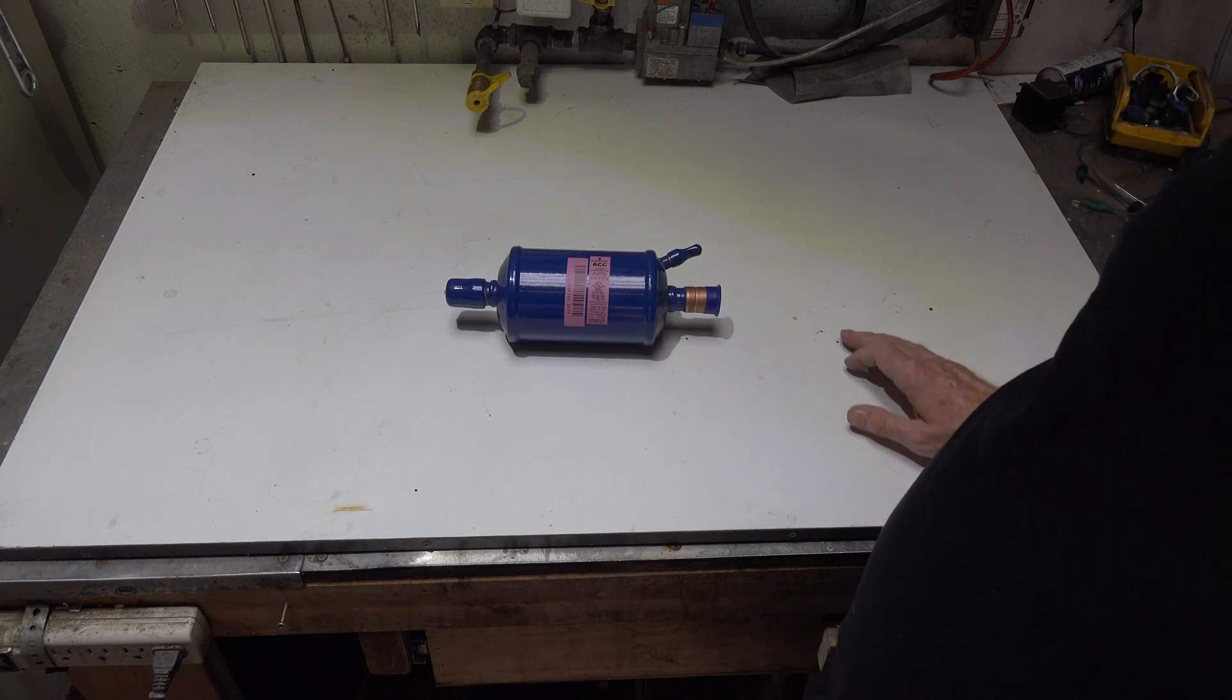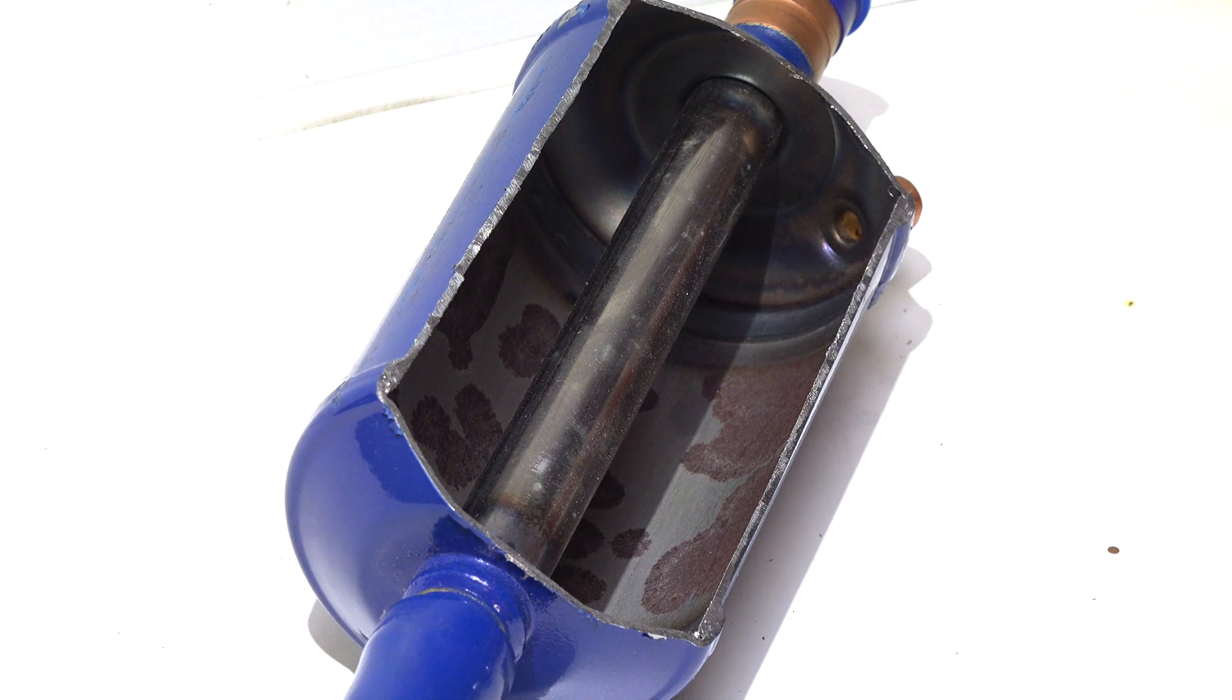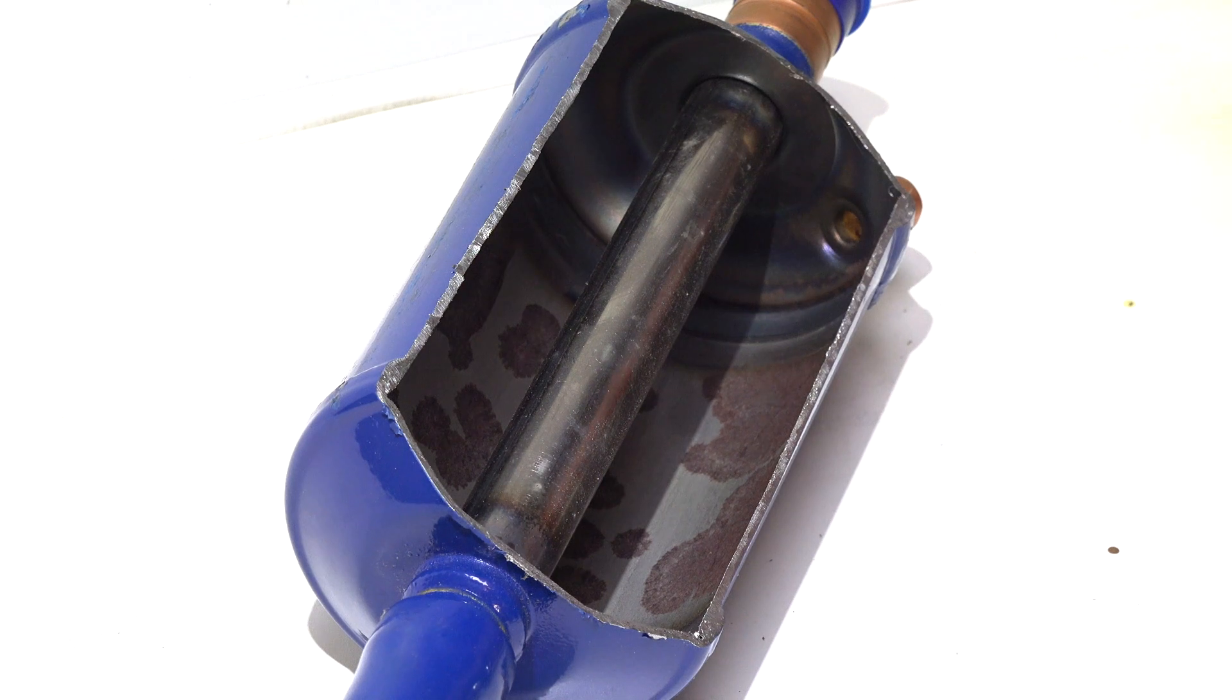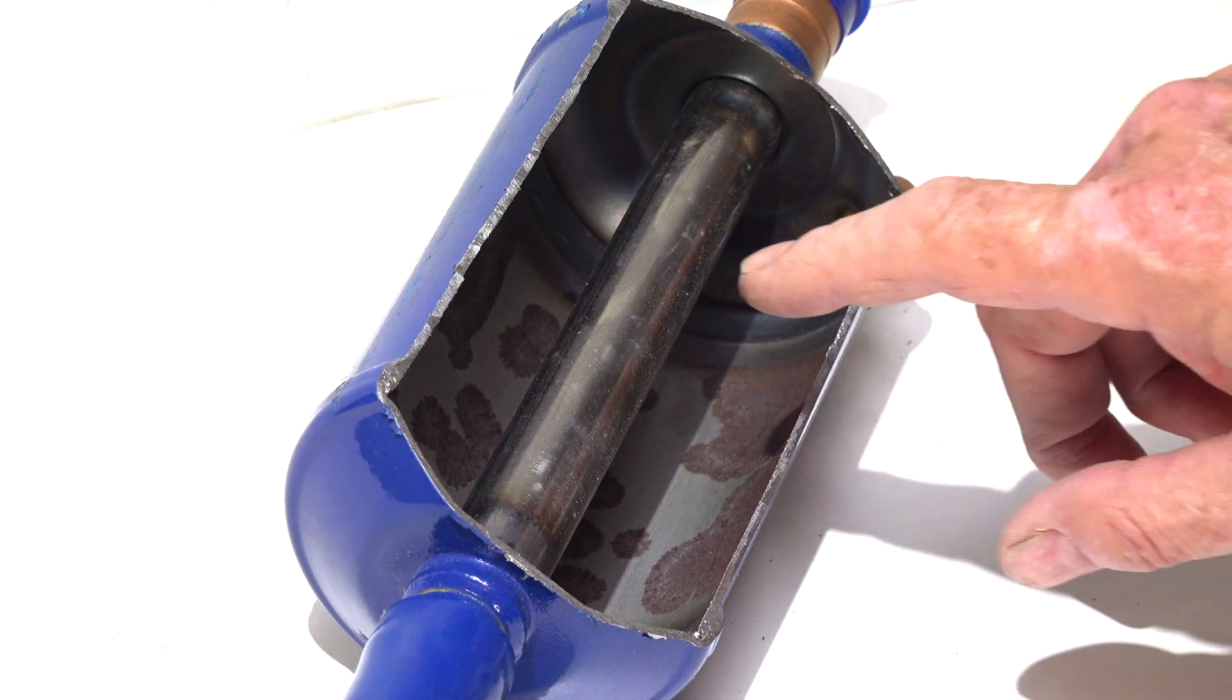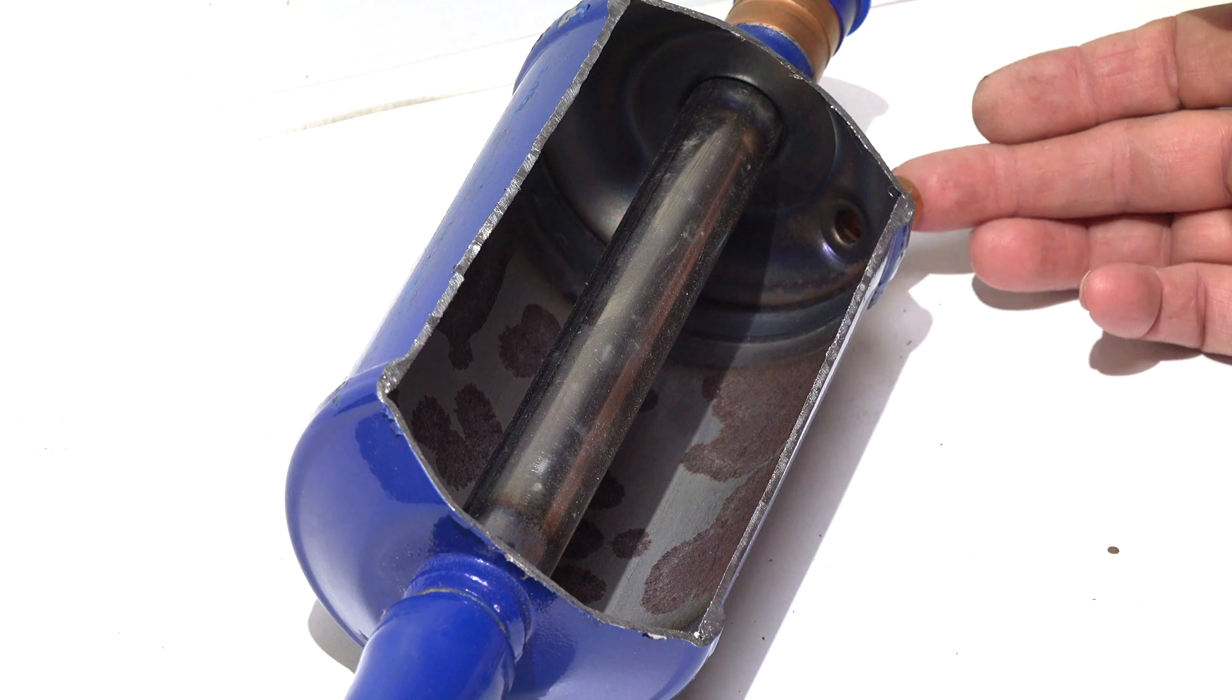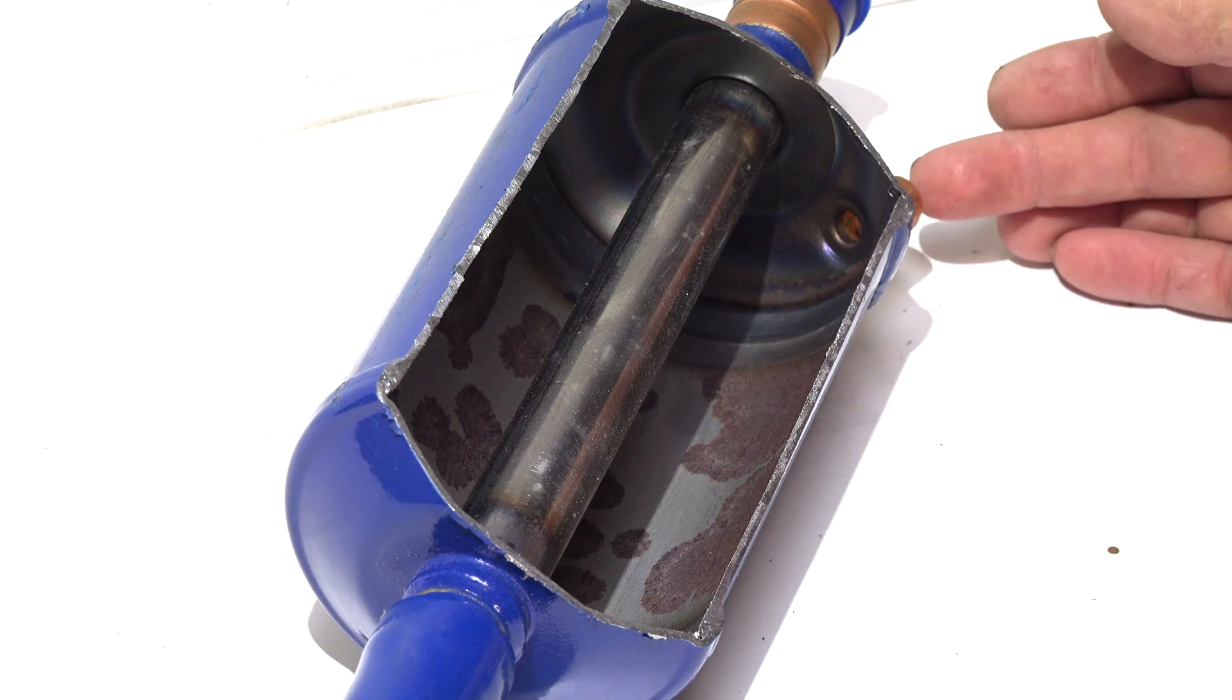Okay, when looking at the inside of this, it really is very simple. It does really look like a muffler. It looks like a suction line dryer to me. So it's just got a pipe go straight through. Now in heat mode this pipe is the suction line, so it's cold. Now there's a tap on the side. Other than the pipes going through, this is the only tap. This goes to the liquid line.